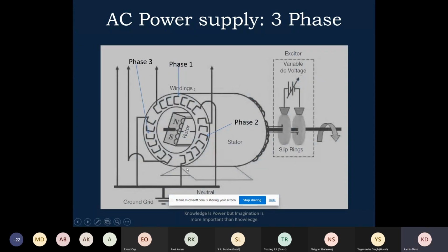Okay, so this is how you look at it here. This is a three-phase generator. So winding 1, winding 2, winding 3, A phase, B phase, C phase. The coils are wound on the stator cores, and this is the rotor. So you can look at the rotor windings, and then you look at it here. This is the A phase, B phase, and C phase terminals, and the other end of the coils is shorted and then grounded.